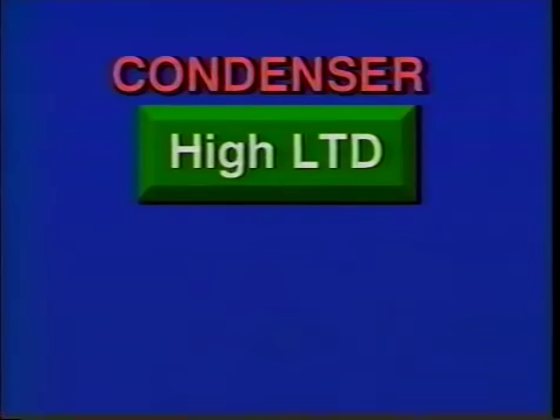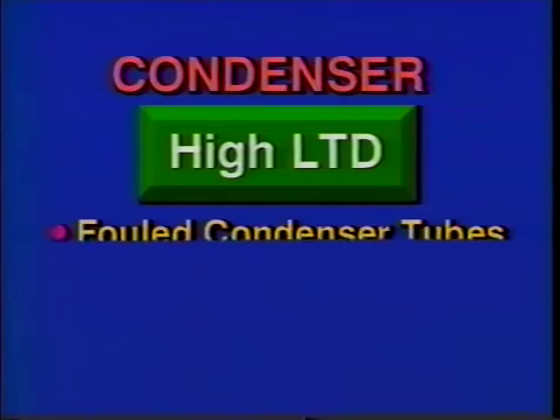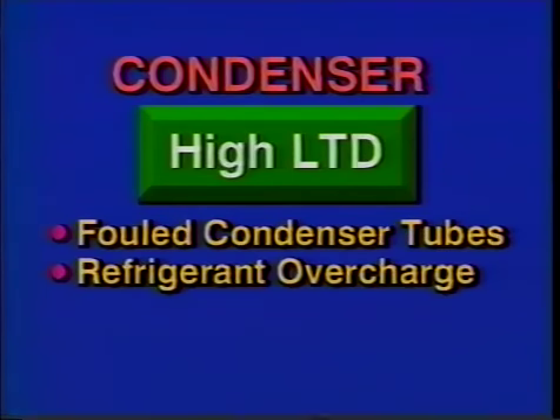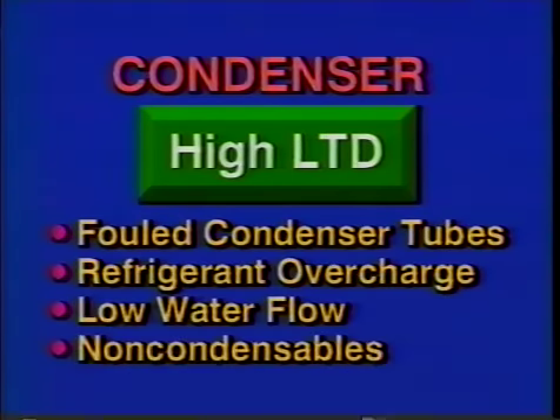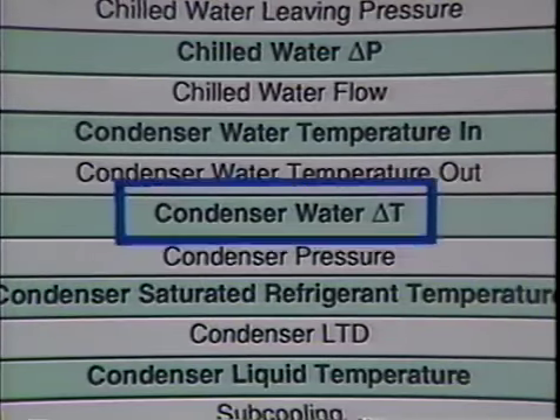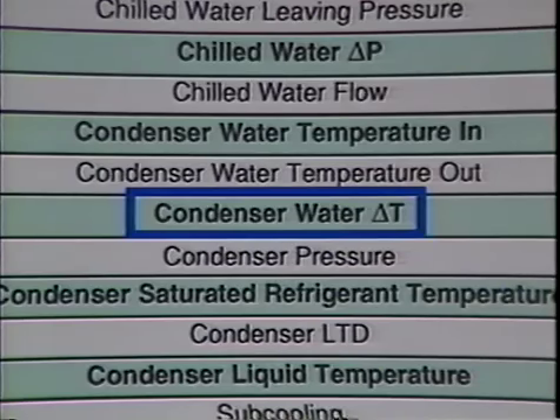If the LTD is high, some of the things we might suspect are fouled condenser tubes, refrigerant overcharge, low water flow, non-condensables in the system. We also need to look at the condenser delta T to help identify specifically what the problem may be. Now let's look at some problem situations.